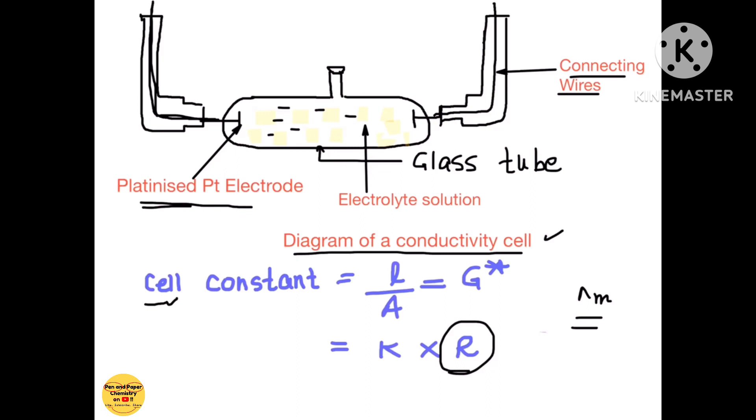Now first of all in this conductivity cell we fill the electrolyte whose conductivity is known at different temperatures and we measure the resistance. So we know the conductivity, we know the resistance, we can determine the cell constant. And what is cell constant? The distance between the electrodes divided by the area of cross section of each of the electrodes that we are using.